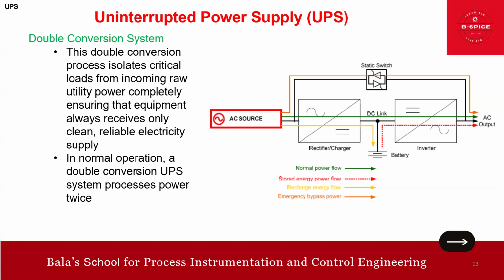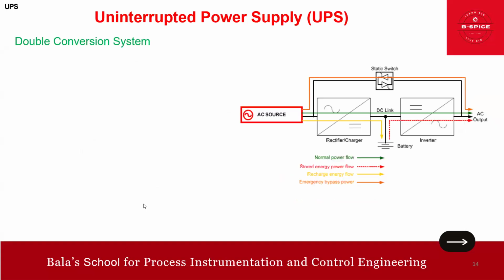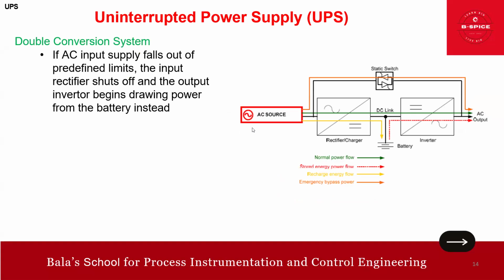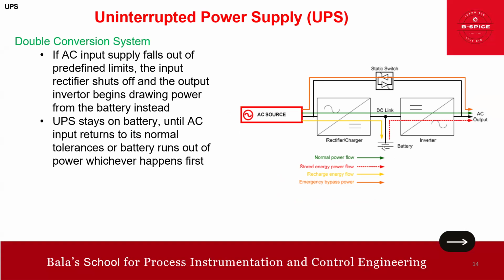So in normal operation, a double conversion UPS system processes power twice. If the AC input falls out of the predefined limit, the input rectifier shuts off, and the output inverter begins to draw power from the battery instead. The UPS system stays on battery until AC power supply returns to normal tolerance or the battery runs out of power, whichever happens first.